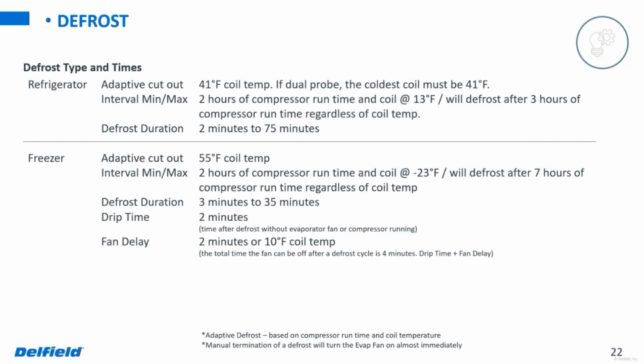On this one here, it does have a default of 3 hours of compressor runtime. So maybe we don't hit that 13-degree coil temp at any point before the 3 hours. Regardless, the unit will go into a defrost. The defrost, like we explained before, is 2 minutes up to 75 minutes, and terminates at 41 degrees.